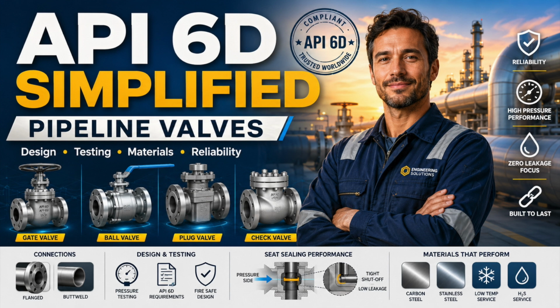You also need to understand seat leakage criteria. Soft seats may be expected to show no visible leakage under defined conditions. Metal seats may permit controlled leakage. Demanding zero leakage from every metal-seated valve may sound conservative, but it may be technically unrealistic or unnecessary. Specify what the process needs. Do not specify what merely sounds strict. Test direction also matters. A unidirectional valve must be tested in the correct direction. A bidirectional valve must demonstrate both directions. A double isolation arrangement must be tested in a way that proves the intended function.